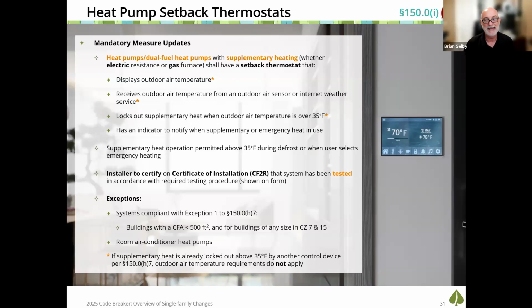It locks out supplementary heating when the ambient outdoor temperature is over 35 degrees, and of course enables it at 35 degrees or below. So that last one basically says that there's an indicator light when that supplementary heating is on, and it can't stay on continuously. So that would be a huge waste of energy. There are other requirements for the installation and testing of these. Of course, there are some exceptions for system types and when those systems are serving smaller buildings, like less than 500 square feet.